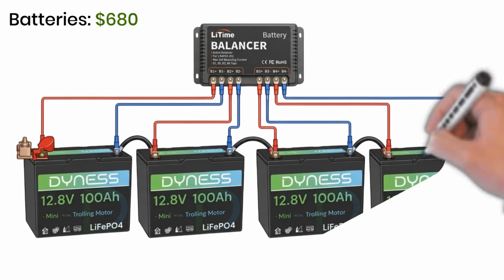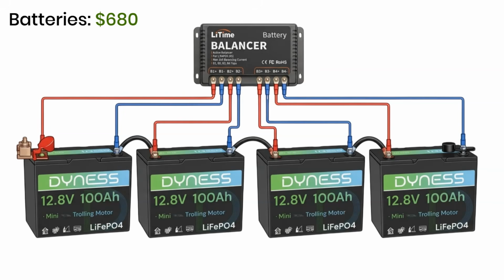Let's talk about one of the biggest hidden costs. Each 12-volt battery has its own built-in battery management system, or BMS. The BMS does a good job protecting and balancing the cells inside that individual battery. The problem is that battery number 1 is not communicating with battery number 2, 3, or 4. Over time, small differences can develop between the batteries. One battery may reach a higher voltage, while another stays slightly lower. As those differences grow, the batteries may no longer share the workload evenly.